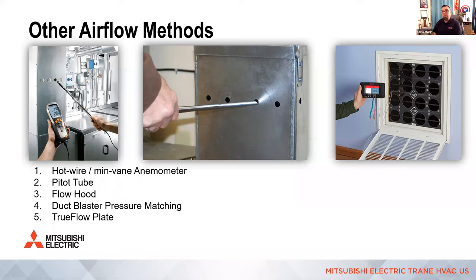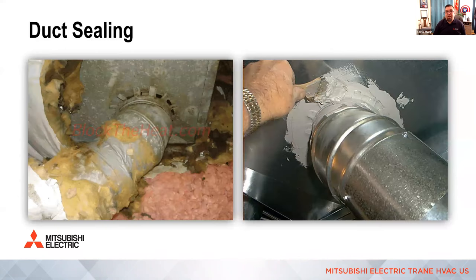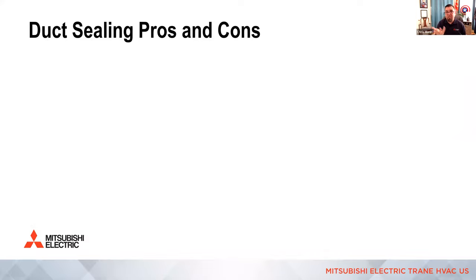And if you know static pressure and you know volume of air, it's a great judge of duct design. Of course, you still need to get the air there, so it should be sealed, right? These are some of the things to look for if you have uncomfortable situations and you think there's a duct issue. Walk through those duct design problems I talked about first, those rules of duct design, and then look for what I would consider the obvious, right?